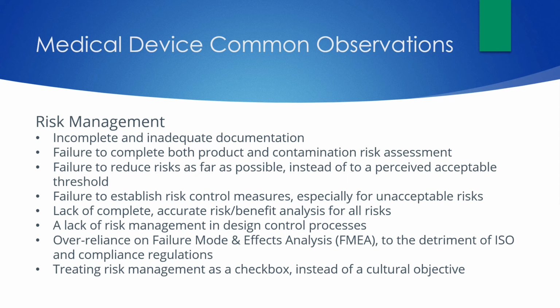Failure to establish risk control measures. Some examples of risk control measures can be extendable tools to eliminate work height, substituting a hazardous chemical with a safer alternative, enclosing dangerous items of machinery or moving parts, or personal protective equipment. Lack of complete or accurate risk-benefit analysis. So there must be documentation, and you have to provide evidence and rationale for all risks. The type of benefit, magnitude of benefit, medical device-related deaths and serious injuries, and non-serious adverse events must be included.